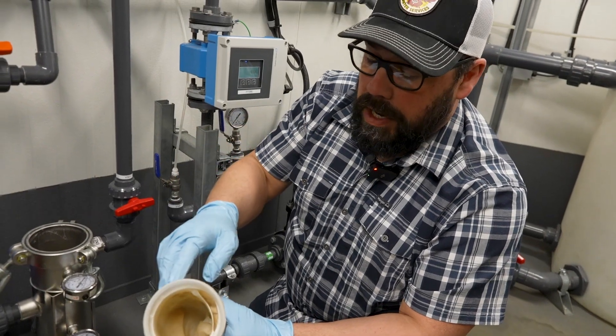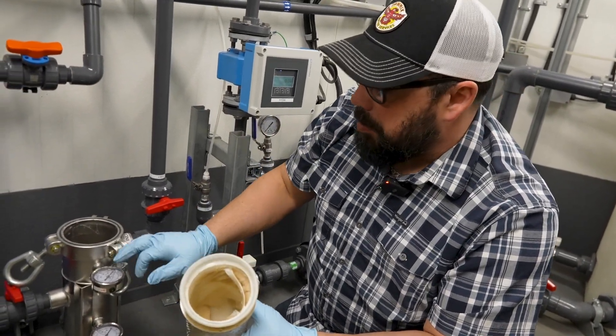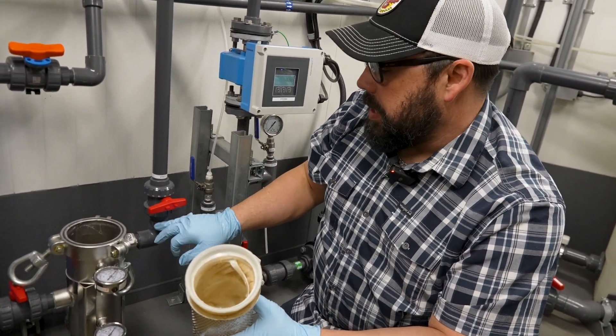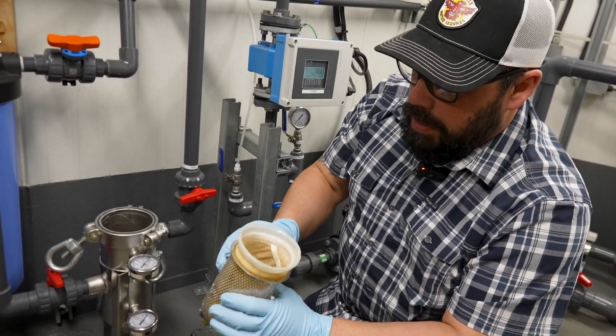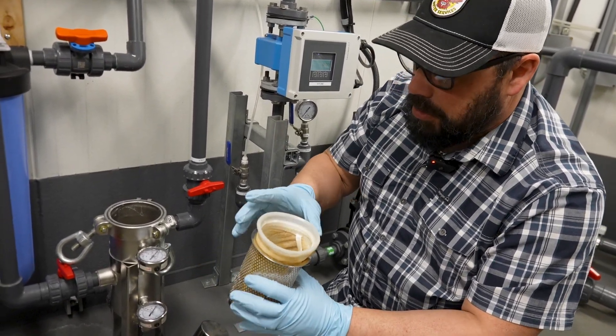Now all your sands and gravels will get stopped in there, and once it's getting plugged up your pressures will start to climb on your inlet side and decrease on your outlet side. And then once you get between 10 psi it's time to change this.